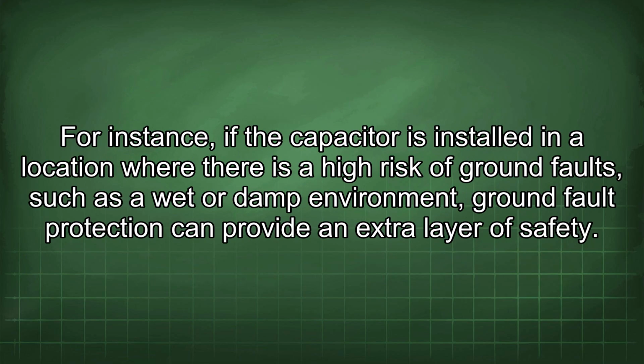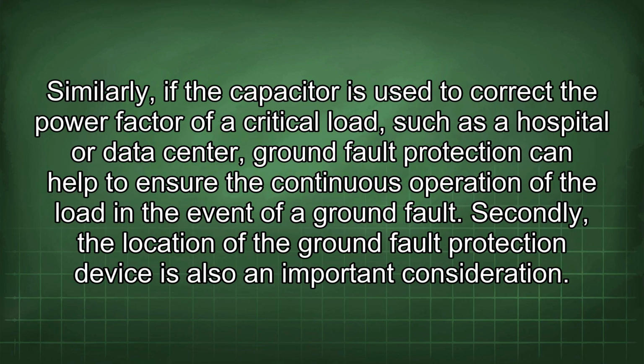For instance, if the capacitor is installed in a location where there is a high risk of ground faults, such as a wet or damp environment, ground fault protection can provide an extra layer of safety. Similarly, if the capacitor is used to correct the power factor of a critical load, such as a hospital or data center, ground fault protection can help to ensure the continuous operation of the load in the event of a ground fault.